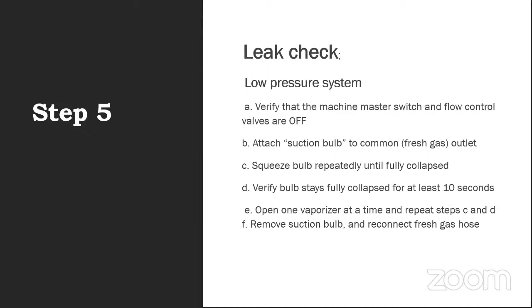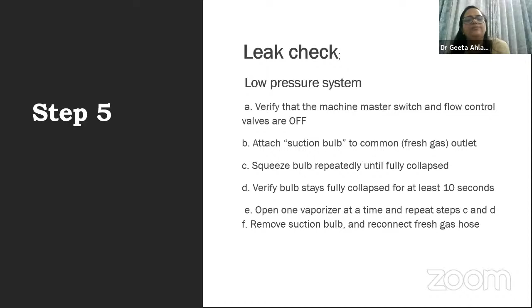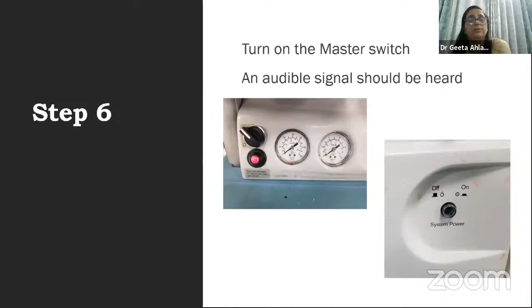This bulb should stay collapsed for at least 10 seconds. Open one vaporizer, then test it again. Open another one, reconnect it. There should be nothing coming out of the fresh gas outlet with the machine master switch off. Only then go ahead. Then when you switch on your master switch, there has to be some audible sign, so that if you inadvertently switch it off or someone else does, you are immediately aware of it.